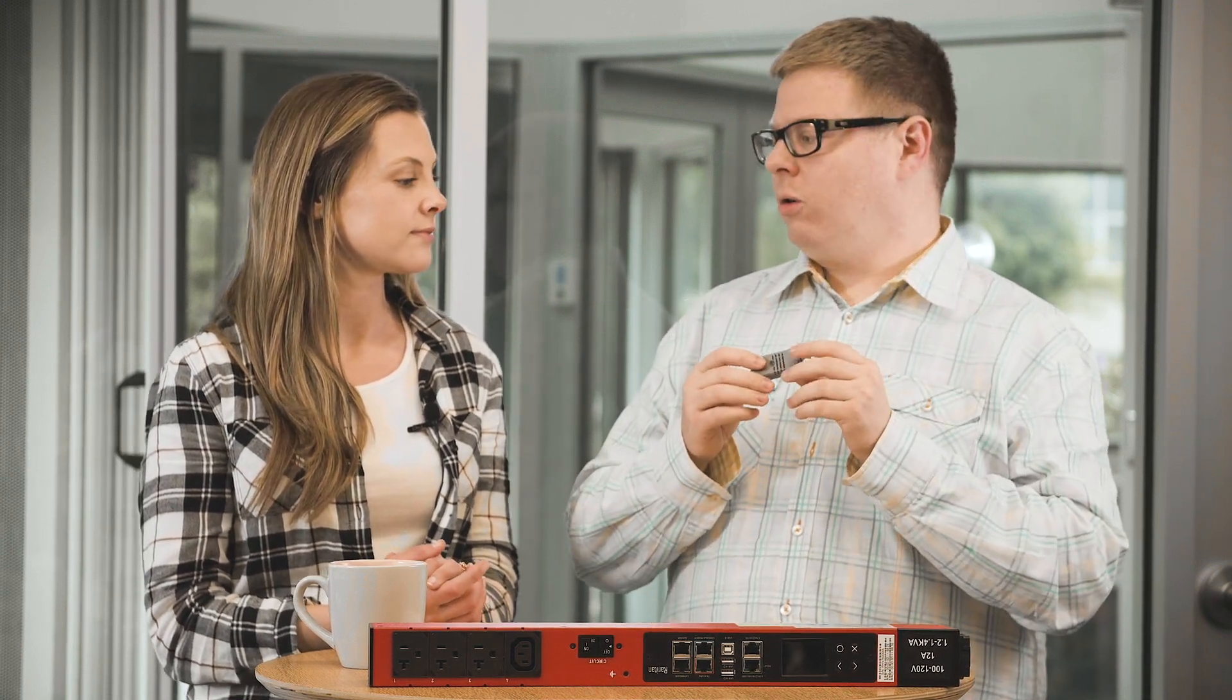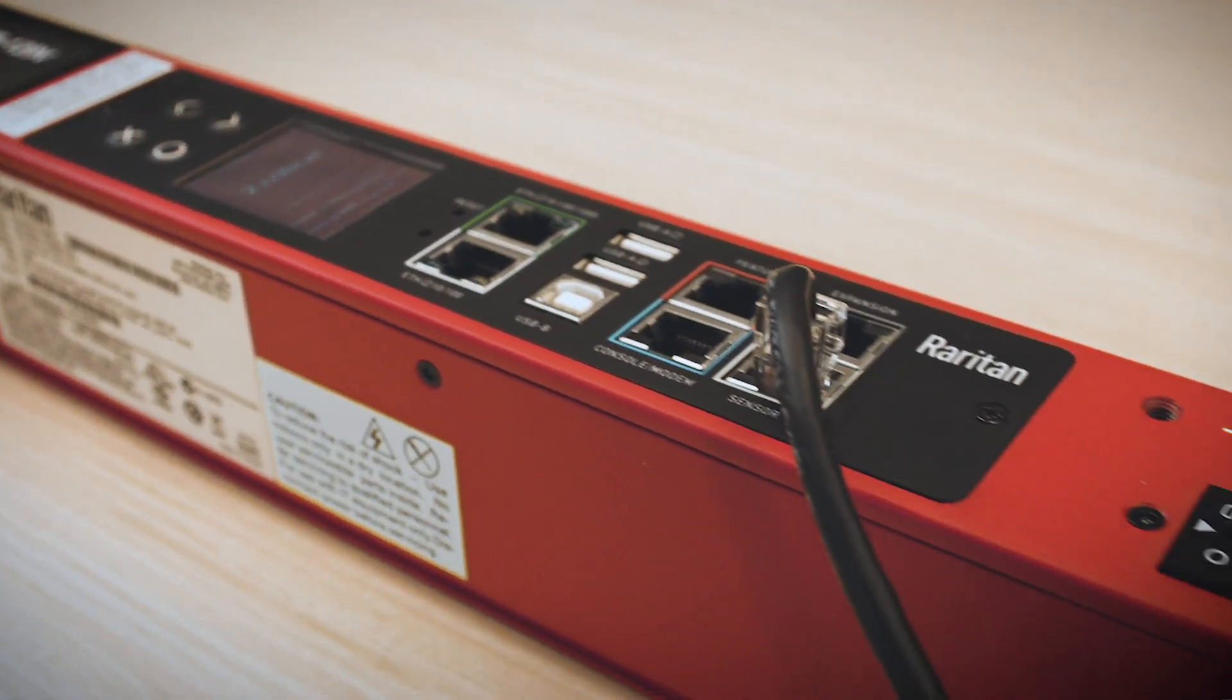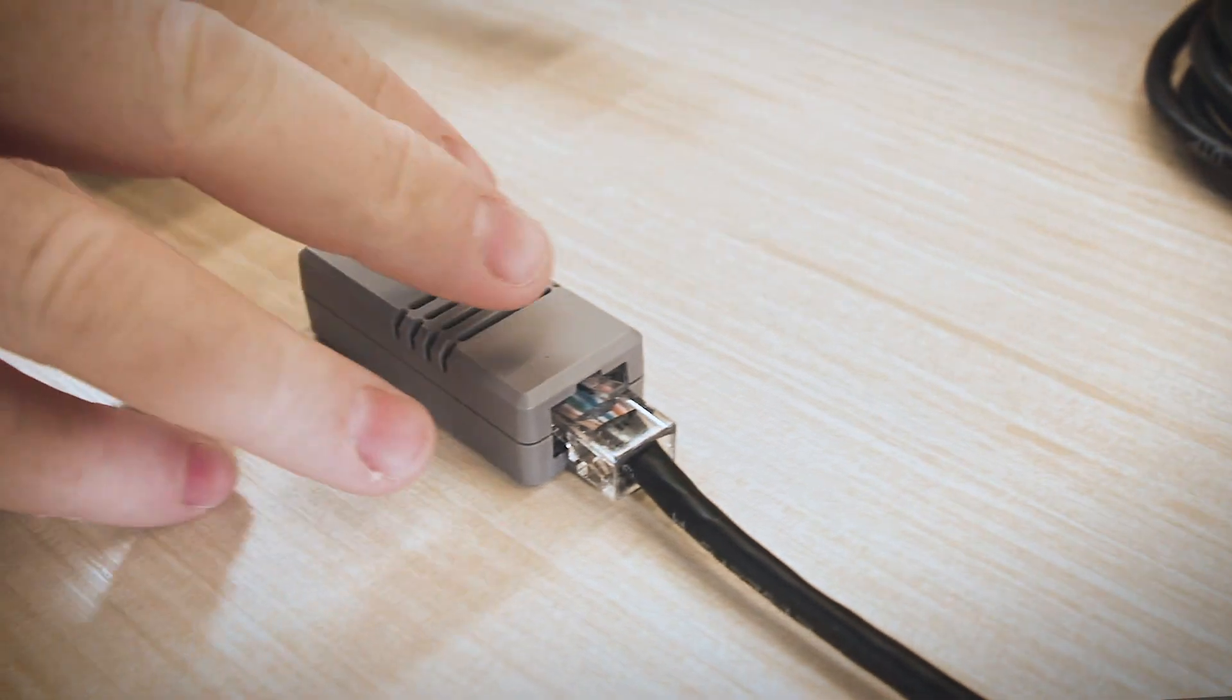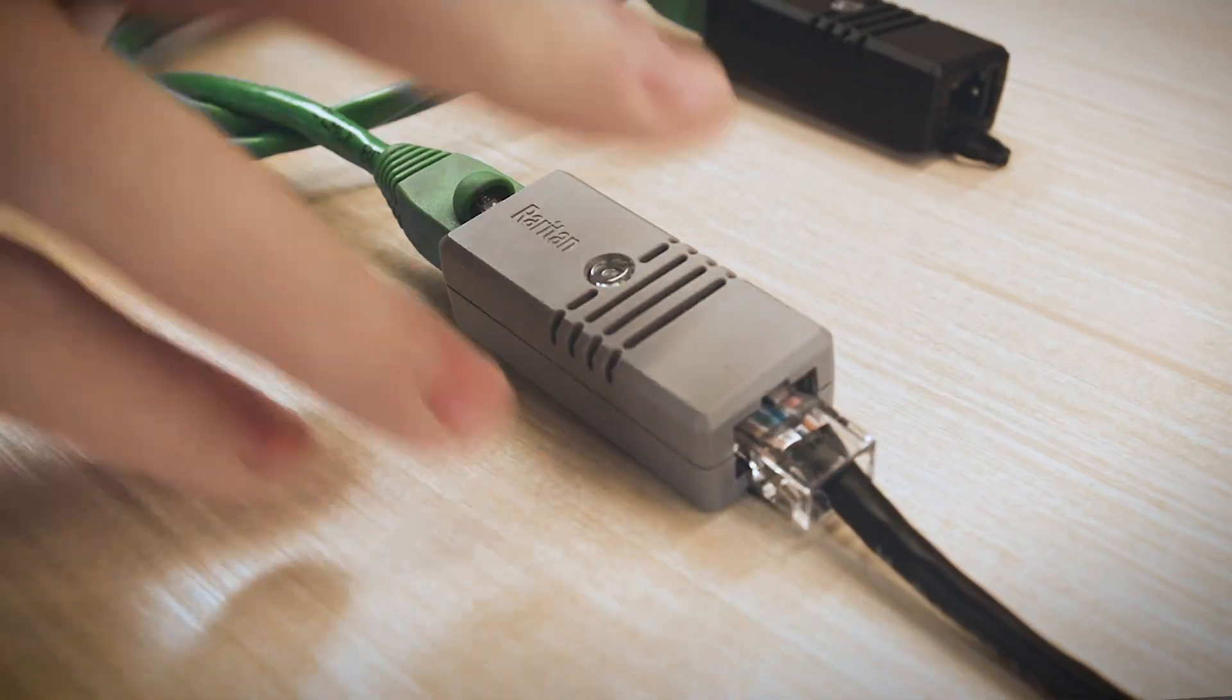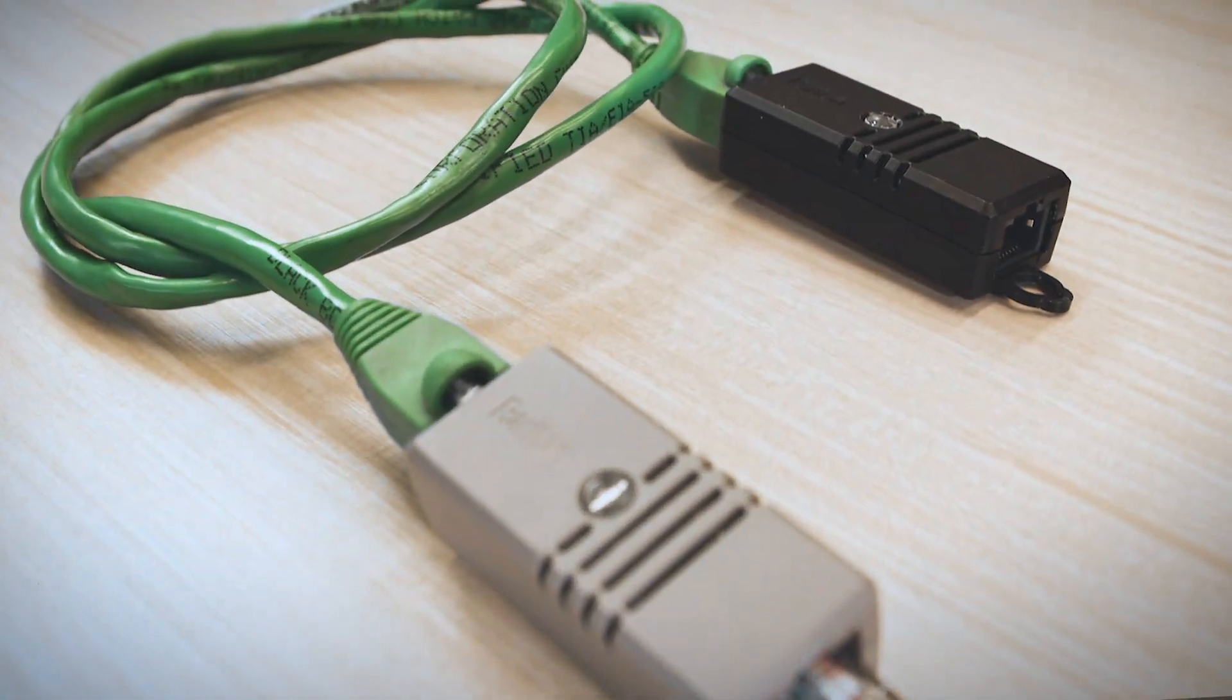Sure thing, Jess. Raritan Smart Sensors offer environmental sensing capabilities in an easy-to-deploy and very small form factor. We have dual RJ45 connectors on each sensor, which allows up to 12 sensor packages to be connected together with simple category cable. Now, we offer a number of different sensors, but our most popular is temperature and humidity.